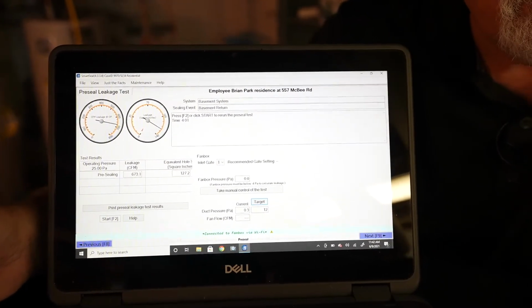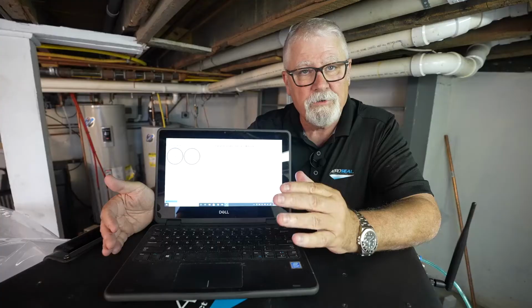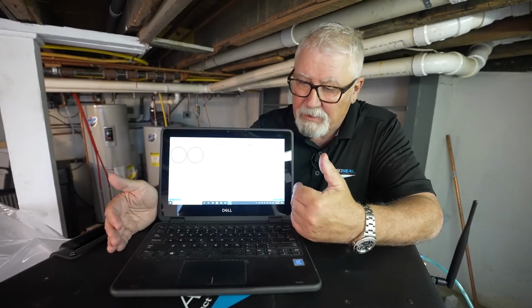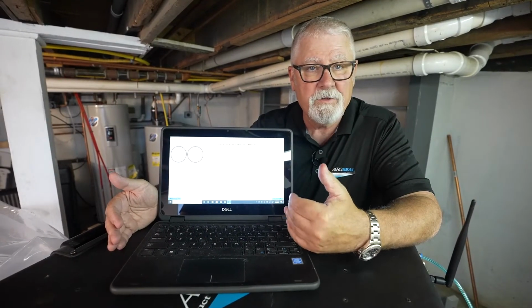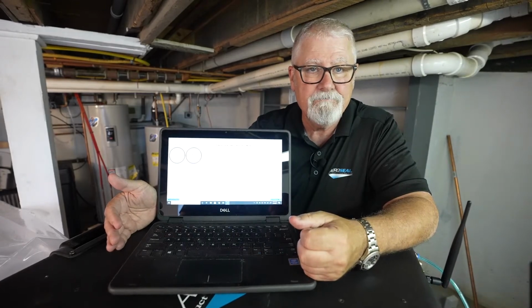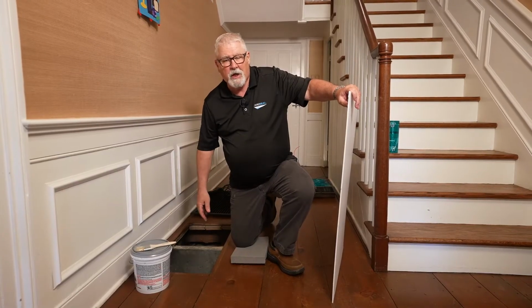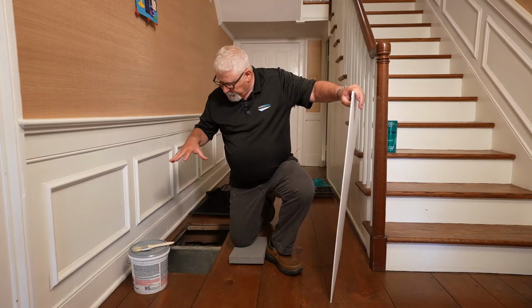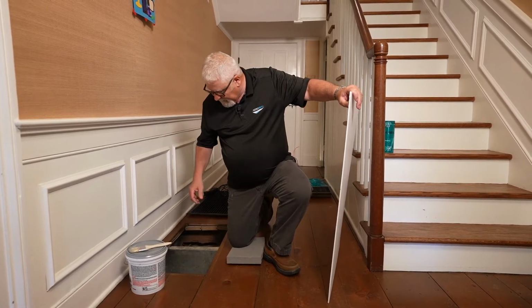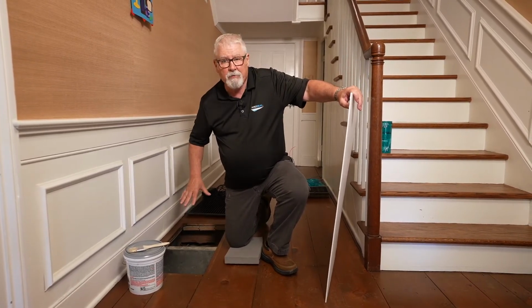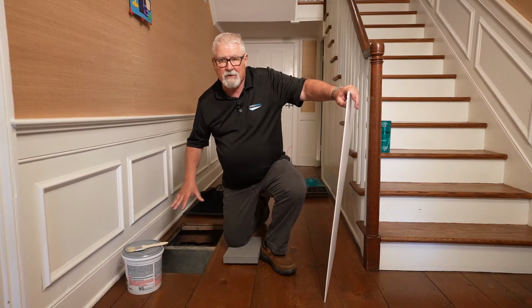So we're going to start opening up and plug it. We're going to try and get that down so that when we start aerosealing, we have a much better chance of getting a good, tight duct system. Okay, as you saw downstairs, we had a lot of leakage. So we've come up and pulled the returns back open again, and we've looked inside. Man, these things are really, really leaky. But the good news is that we can get down inside.